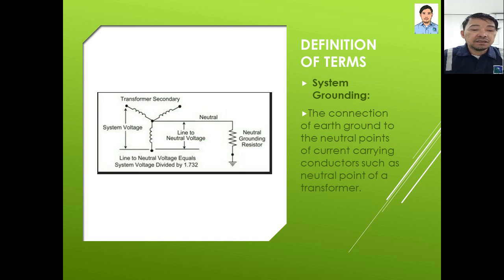Here is the system grounding. What you see is a three-phase wye or Y configuration of the transformer secondary side. A wye connection is a three-phase circuit in which all three loads are connected at a single neutral point. The advantage of this configuration is that it can provide multiple voltages. This carries a fourth neutral conductor. There are two types of system grounding: solidly grounded system and impedance grounded system.